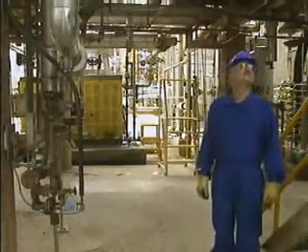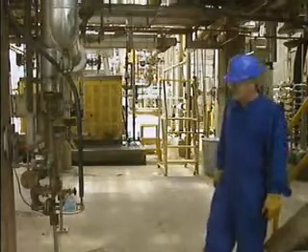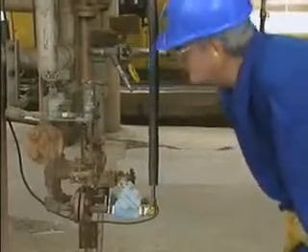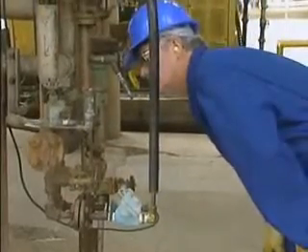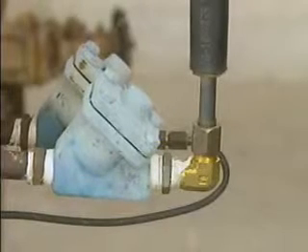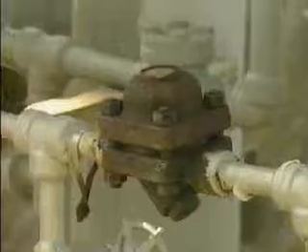But as with other types of inspections, you need training and practice to be able to perform the inspection effectively. Begin by simply looking over the trap for condensate or steam leaks. Leaks typically occur at piping connections and at the steam trap's body-to-bonnet connections. Next, see if live steam is being discharged from the trap.